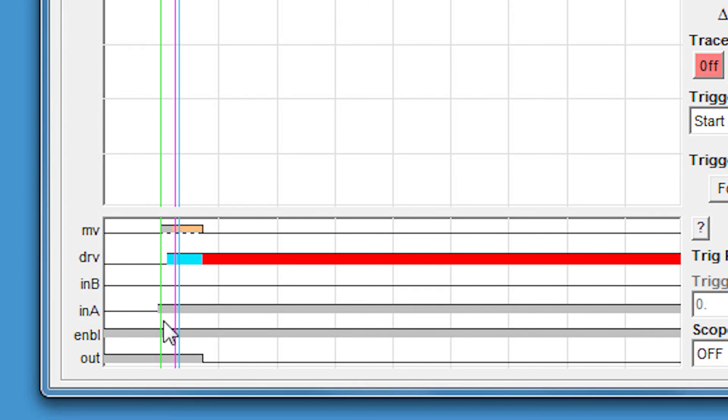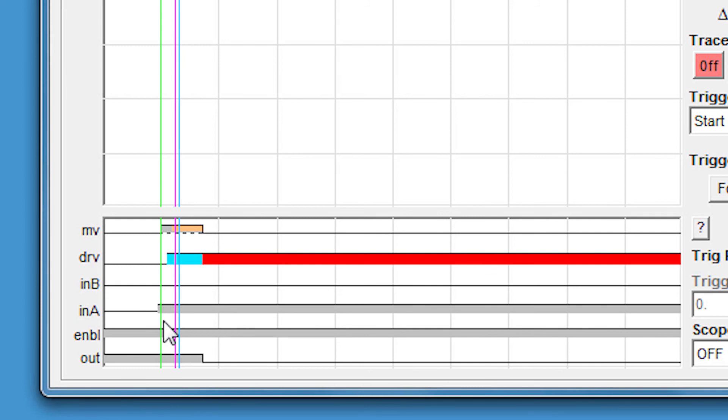We know from manually overriding these inputs and triggering it, that the start of the move was exactly when we clicked the input A. That makes sense that it was asserted right when we clicked that to initiate the move. This is very useful when you're using hardware inputs. Let's say you have a faulty wire or even the software that might not be sending out the correct signal all the time. You could make a move and look at the strip chart like we are now and see exactly when these inputs are asserted. If there is a problem with a line or some software, you'd see where that occurs using the strip chart.